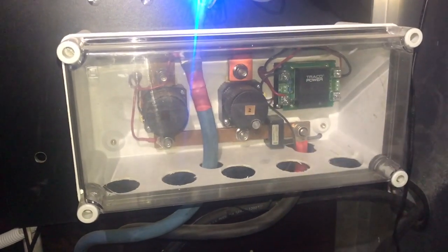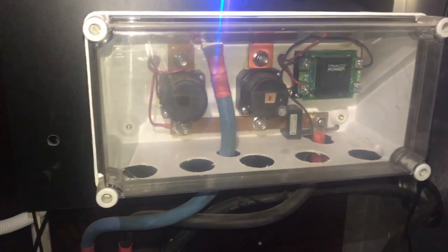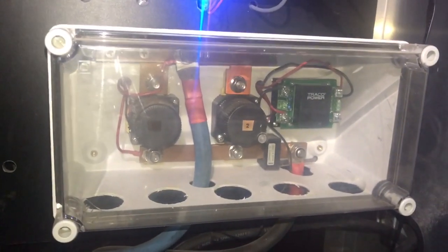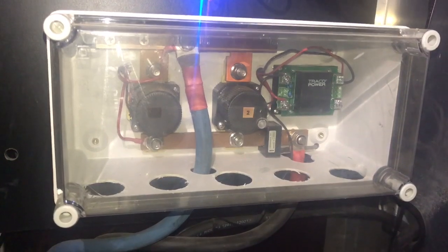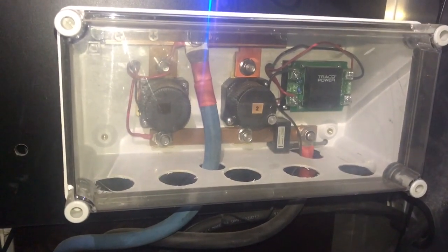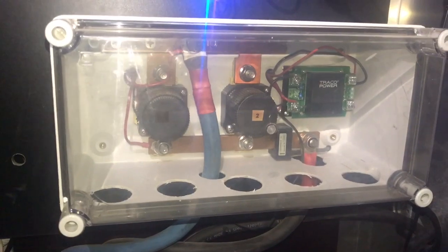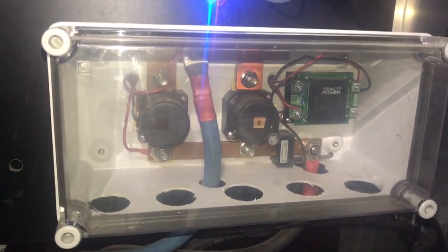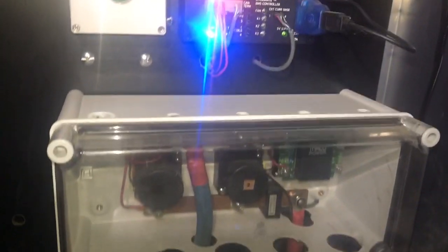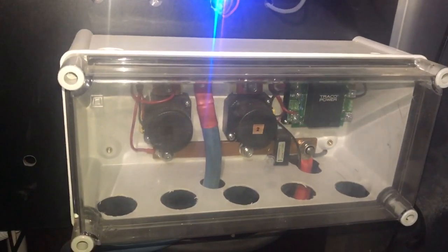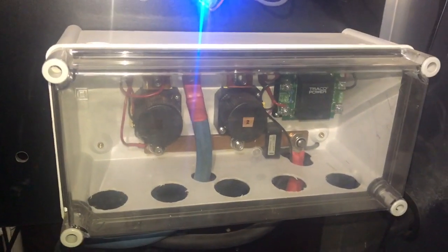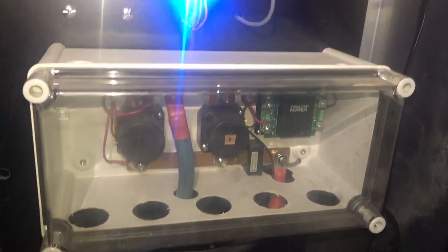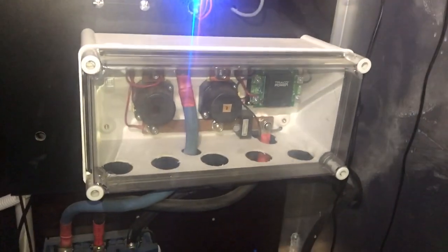I would definitely suggest, don't skimp if you're building a system like this on these contactors. You want ones rated for a large number of breaks, much higher current rating, and really high temperatures, because you do not want those to weld - if they weld, you basically toast your pack. The BMS has the final say, and when you're charging at say 20 kilowatts of power, if the BMS says stop and the electronics for whatever reason has a heart attack and disagrees, you want those contactors protecting your pack, otherwise it's toast.